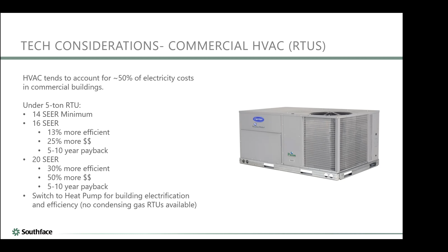And so you're paying for the same labor to lift it on the roof with a crane instead of the labor to set up a more complex system like in a split system. Another thing you can do with RTUs is switch over to heat pump heat if you have a gas furnace RTU, and that's good if you're trying to electrify your building and get away from fossil fuels. It also allows you to have more efficient heat, because as far as I've seen, there's no such thing as a condensing gas RTU furnace. So 80% is the highest efficiency you can get in a gas RTU, whereas heat pumps let you have coefficients of performance of 3 to 4, somewhere in there.